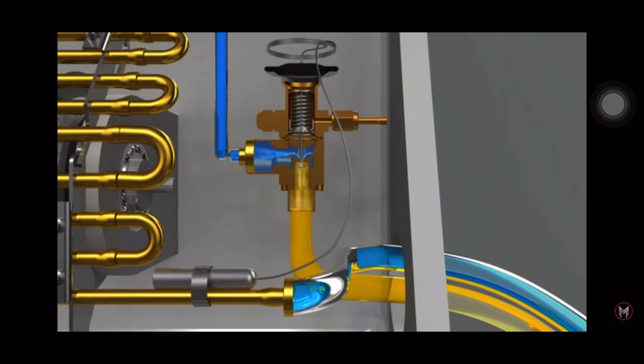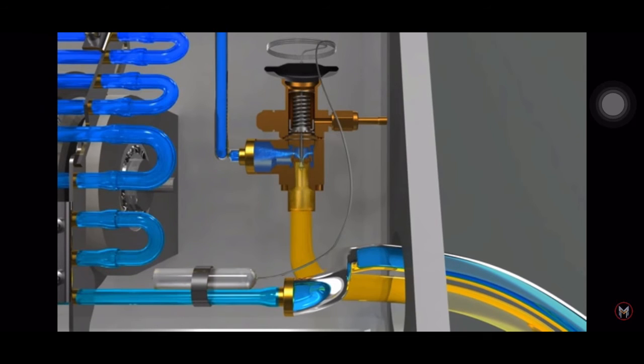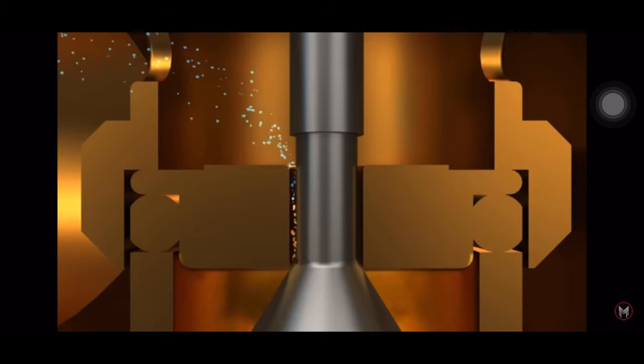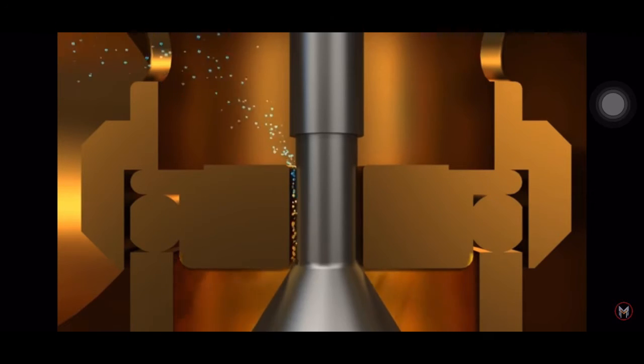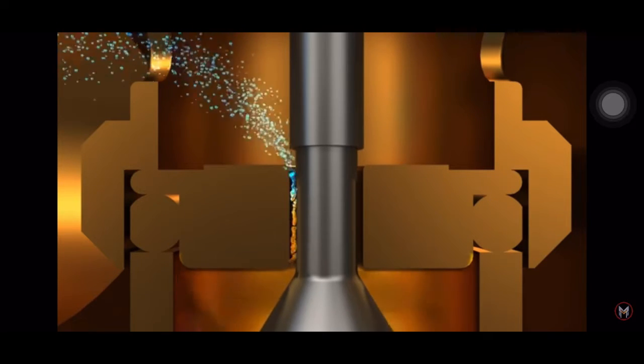The expansion valve is connected to a sensing bulb that detects heat. The sensing bulb is installed at the exit of an evaporator and detects temperature. Inside the storage is fluid sensitive to temperature changes, and as the temperature at the exit of an evaporator rises, the gas pressure rises, which in turn presses on a spring to send more refrigerant to the evaporator.